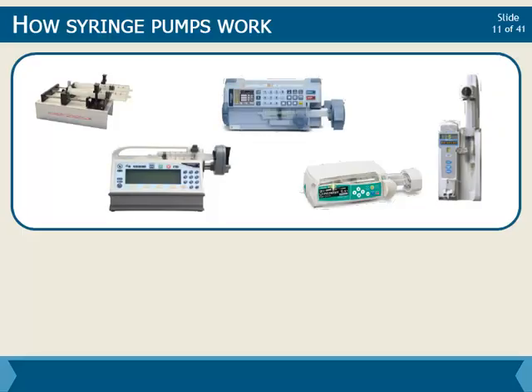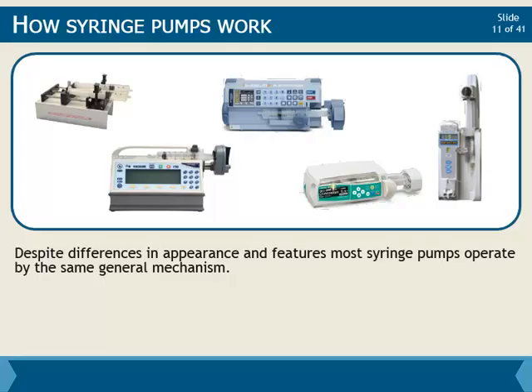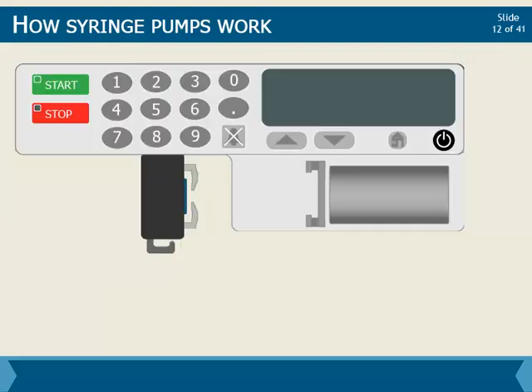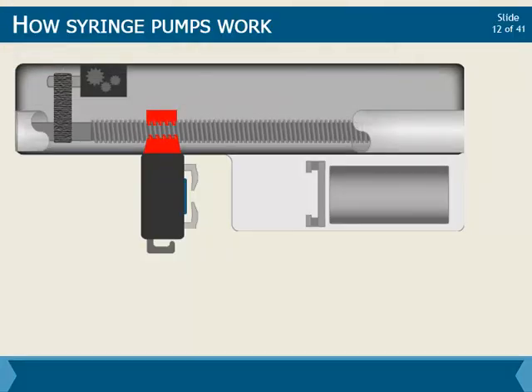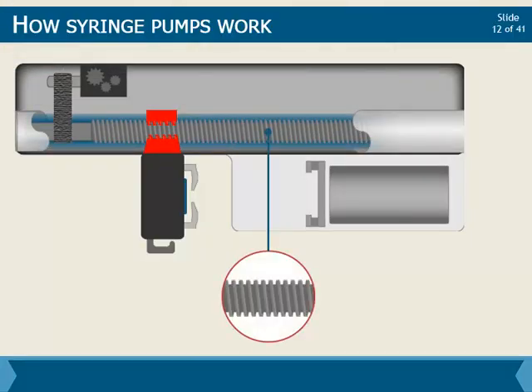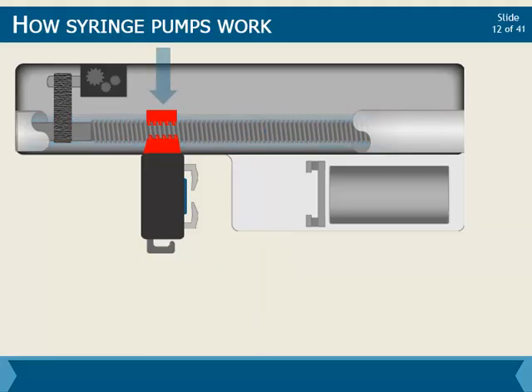Syringe pumps have changed a lot over the years, and currently there are many makes and models in use. Yet, despite differences in appearance and features, most syringe pumps operate by the same general mechanism. It is important to first briefly discuss this mechanism, as it will be important to understanding some of the topics in these modules. Here is one mechanism of syringe pump operation. Within the device is a long drive shaft with threads. Clamped onto this is a split nut, shown here in red. The nut is attached to the part of the pump that pushes down on the syringe plunger.